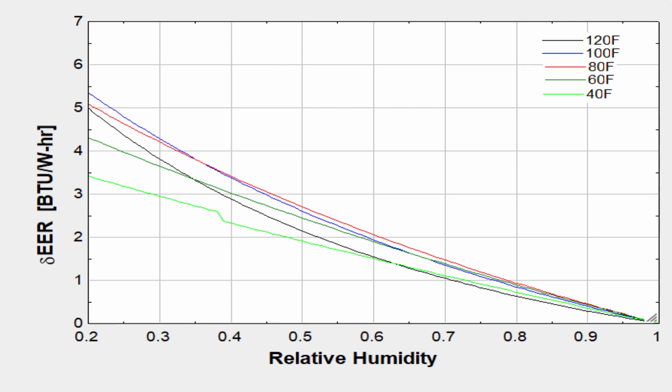Before designing could start, calculations had to prove that implementation of an evaporative cooling system would show a tangible benefit. This graph displays the relationship between the increased efficiency that is caused by using the mist to cool the air and the amount of humidity already available in the air. On very humid days, very little evaporative cooling is possible, which prevents substantial increases in efficiency.